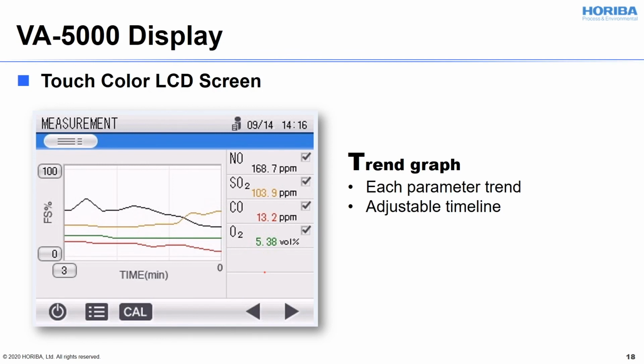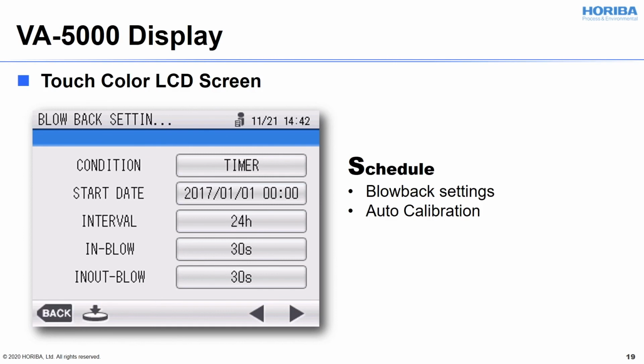You can adjust the timeline, of course. If you don't need to show specific parameters, you just uncheck the box on the right. In the menu, there is a setting mode. You can schedule blowback timing. This is used to put air in the probe backward to the sample point so that dust collected on the filter goes back to the process. This function helps the performance of the probe filter and makes the lifetime longer for the probe and the pump. You can schedule the starting date, time, interval, and how long you want to blow. As well as the blowback setting, you can schedule auto calibration as well.